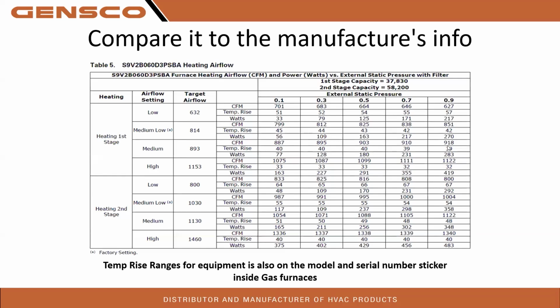So temperature rise range just for equipment is on the model and serial number sticker. The main sticker should be there. This should also have LP and NG pressures first and second. That is a UL listing requirement to put it on the manufacturer's label. So use everything in the install and service facts to bring the data home for you. Some of it you're going to have to get yourself because the manufacturer doesn't know what the duct system it's going to be tied to, right? Doesn't know if it's a gas furnace and coil, what coil you're going to mate it up with. So we're going to have to collect this data.